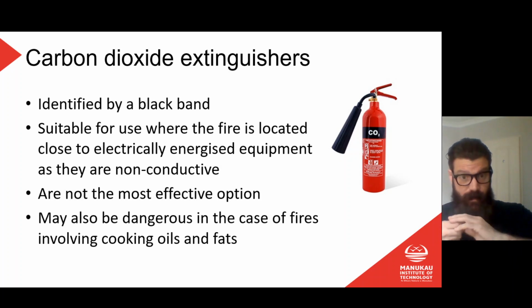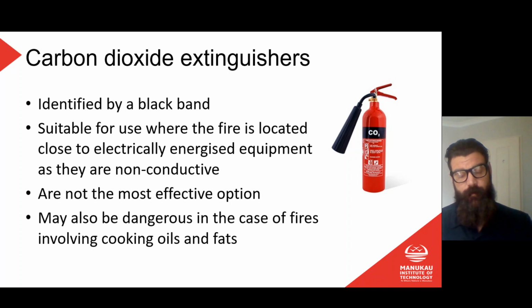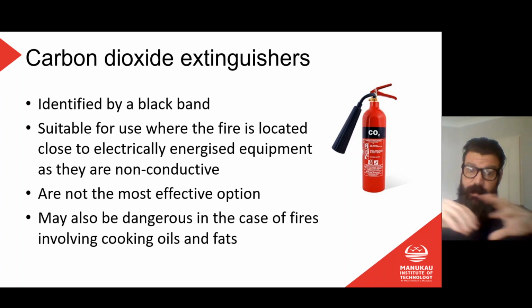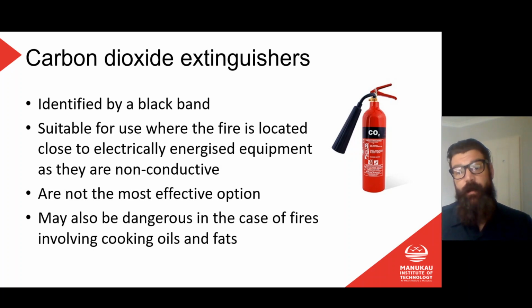But generally, that continuous spray is what's going to put out the fire, not just squirting the CO2 and then CO2 in the atmosphere extinguishing the fire. It's the actual stream. And then it says at the bottom, may also be dangerous in the case of cooking oils and fats. So again, we could extinguish the fire by spraying the CO2 on it, and the CO2 displaces the oxygen around that fire and therefore puts it out. But if you think about it, it's coming out as a pretty high pressure jet of gas from the extinguisher, and so in the case of a fire on a liquid like an oil, that could fling that oil all over the place. You can imagine spraying high pressure air into a bucket of water, the water's going to flick everywhere, and it's the same thing if we spray high pressure CO2 onto a liquid fire. That liquid could spray everywhere, and then you've got a bit of napalm on your hands, and then it's obviously going to continue to catch fire wherever that stuff lands. So there's a few issues with CO2 fire extinguishers, but you will often see them around switchboards because they're probably the safest one to use for an electrical fire.